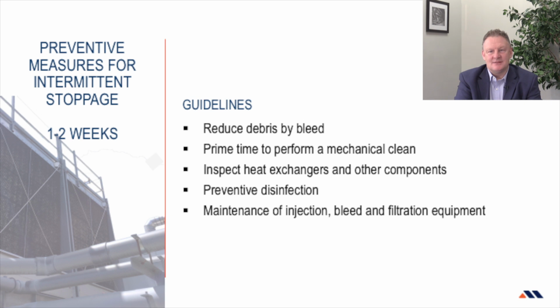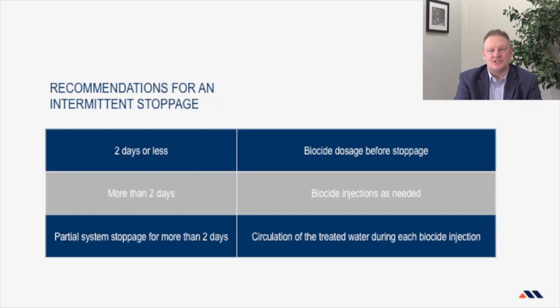Prior to the stoppage, it is important to adjust the bleed to reduce the concentration of silt and debris. A scheduled outage is the best time to perform mechanical clean and preventative disinfection using halogen-based chemistry. This is also a good opportunity to inspect the different components of the system to detect any potential problems and complete preventative maintenance on the chemical injection system, the conductivity controller, the online probes, the analyzers, and side stream filtration unit. Short stoppages may seem harmless, but preventative steps must still be taken as soon as there is a potential of stagnant water due to the risk of bacteria proliferation.